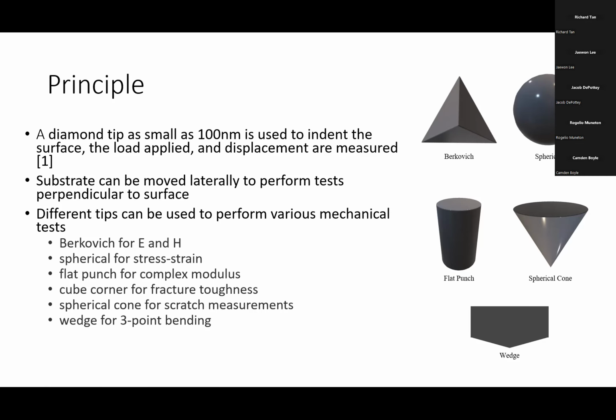We can see some to the right here. The triangular prism tip right there is for Young's modulus and hardness. A spherical tip can be used for stress and strain. The flat punch, the cylindrical tip, would be used for looking at the complex modulus of your sample. You have a cube corner for fracture toughness, a spherical cone, which would be used for scratch measurements, and you can use a wedge tip for a 3-point bending test.